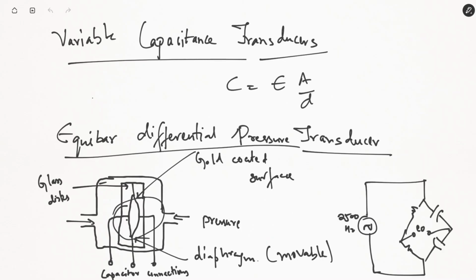If an unequal pressure is on the two sides of this device, that will result in a capacitance value that will cause an output voltage from the bridge that will not be equal to zero. So you can get an idea of whether your pressure is balanced at this time or imbalanced.